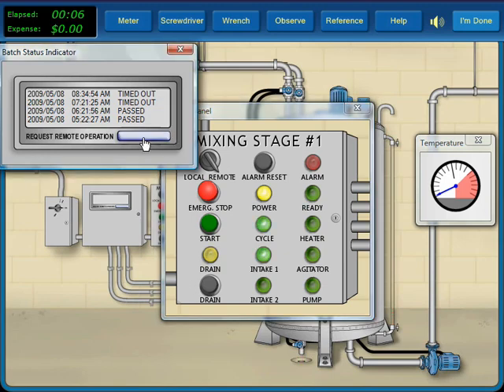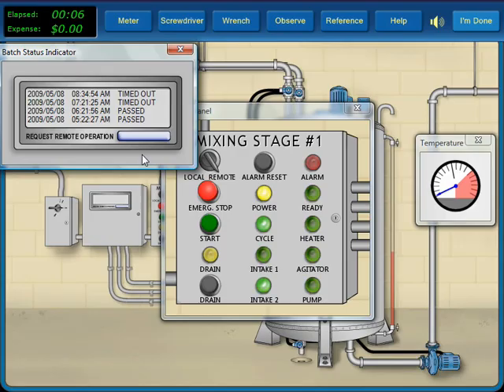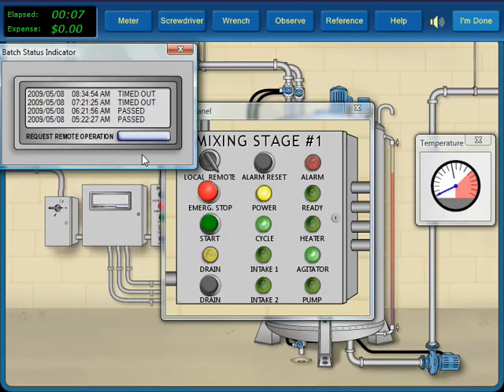Restarting the system, we see the tank begin to fill with the first fluid and then switch to the second fluid. Once the tank is full, we hear the agitator start, indicating that we have repaired the malfunction.